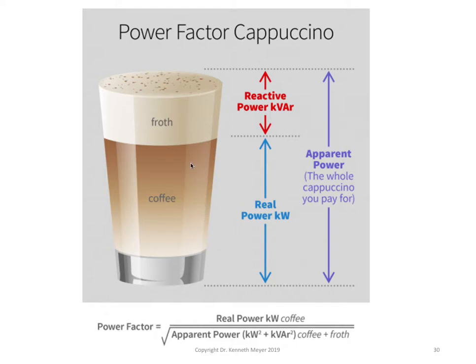So when we're adding capacitances into an industrial installation, we're trying to reduce the reactive component by adding capacitors, which are at 180 degrees from the inductors in the circuit, therefore cancelling out or making the froth on the top very much smaller, so you'll end up with more real power and less reactive power.